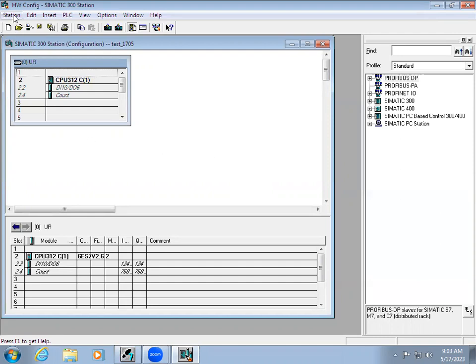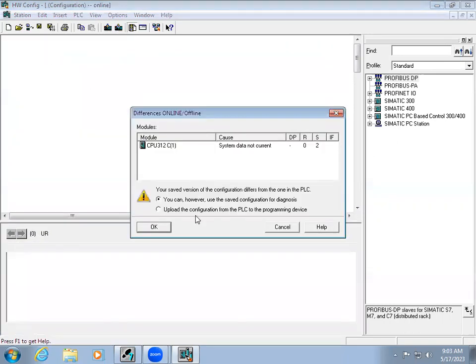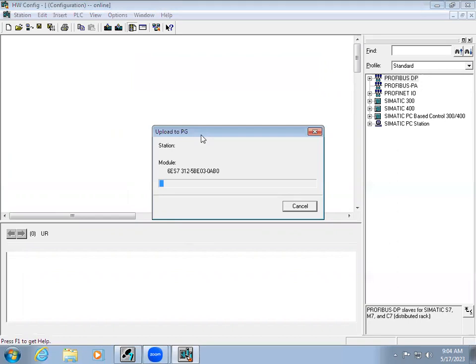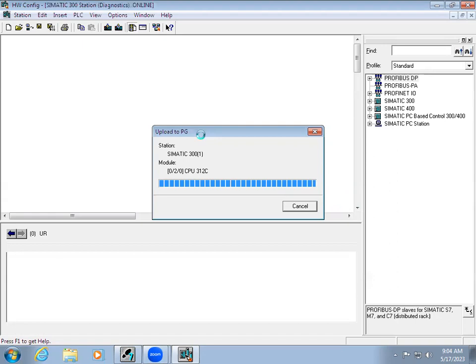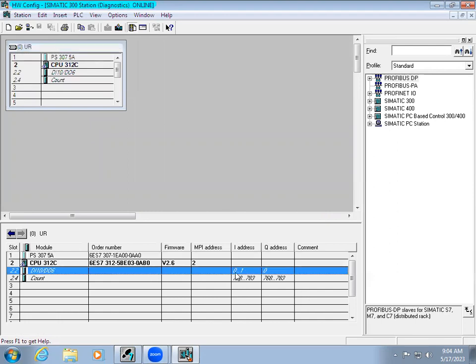For hardware configuration in the station, go to Open Online. When you give Open Online, it will ask you — you can save the configuration for diagnosis, or you can upload the configuration from the PLC to the programming device, which is the PC. When you give Open Online, you can see it uploads the hardware configuration and you can see what address has been used for the digital I/Os in our logic programming.